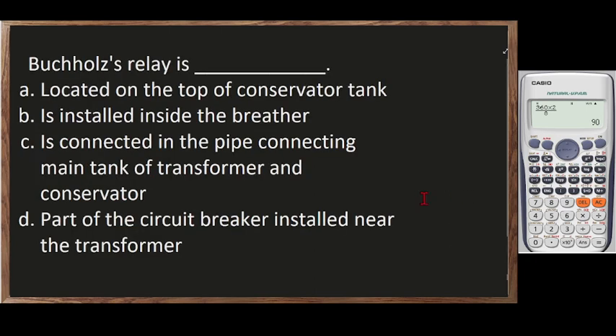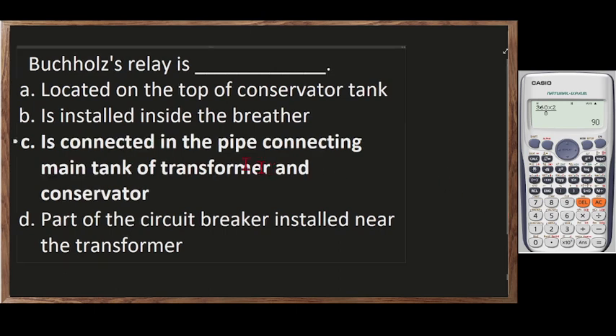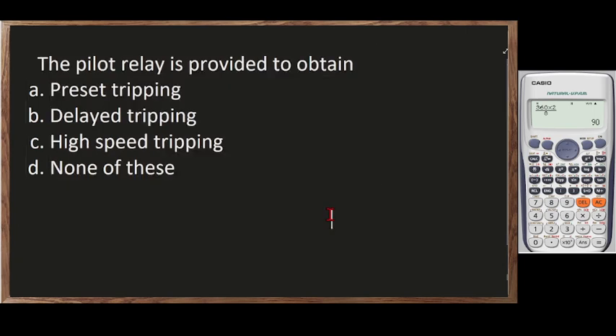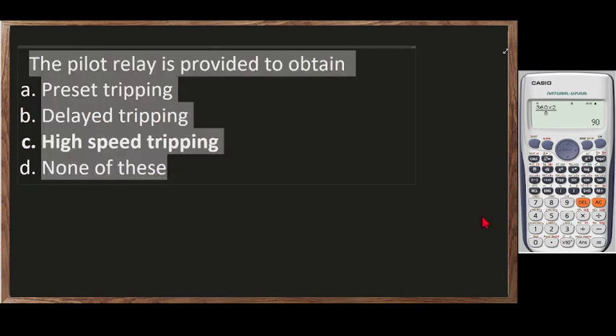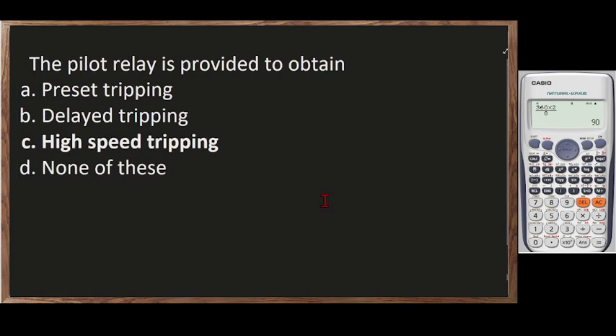Okay. Buchholz relay is blank, located on the top of the conservator tank, installed inside the breather, connected in pipe connecting the main tank of the transformer and the conservator, part of the circuit breaker installed near the transformer. The correct answer is letter C. So it is connected on the pipe connecting the main tank of the transformer and the conservator. Okay. The pilot relay is provided to obtain blank, no, preset tripping, delayed tripping, high speed tripping, or none of these, no. So the correct answer for this one is letter C, no, the high speed tripping.